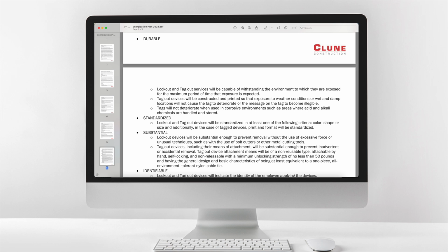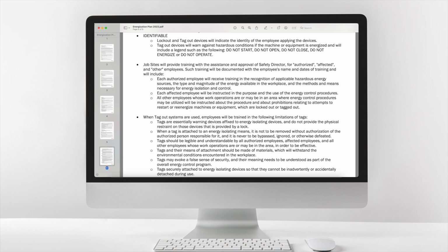Tagout device attachment means will be of a non-reusable type, attachable by hand, self-locking, and non-releasable, with a minimum unlocking strength of no less than 50 pounds and having the general design and basic characteristics of being at least equivalent to a one-piece, all-environment-tolerant nylon cable tie. Identifiable lockout and tagout devices will indicate the identity of the employee applying the devices. Tagout devices will warn against hazardous conditions if the machine or equipment is energized and will include a legend such as the following: do not start, do not open, do not close, do not energize or do not operate.